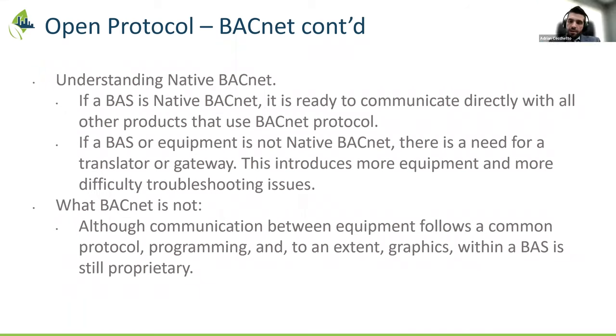I definitely see that all the major vendors on the BAS side absolutely have a BACnet solution out there. On the equipment manufacturer side, we're seeing a lot of equipment supplied with either their own controller that they've developed, or a controller that maybe they've rebranded. Usually those scenarios have pretty good descriptors and pretty good functionality, kind of what we touched on before.